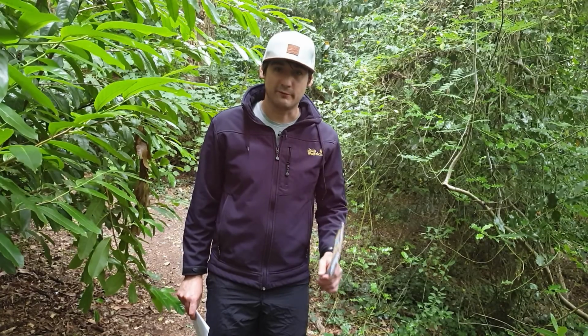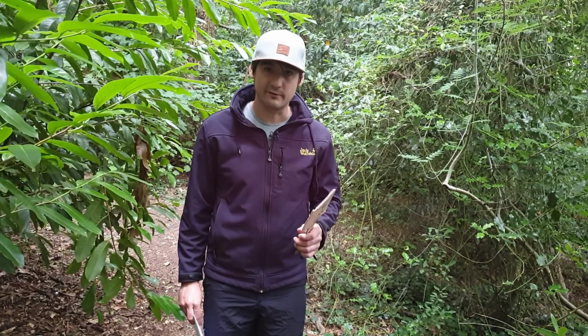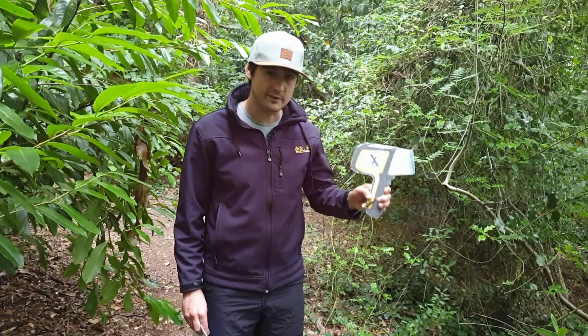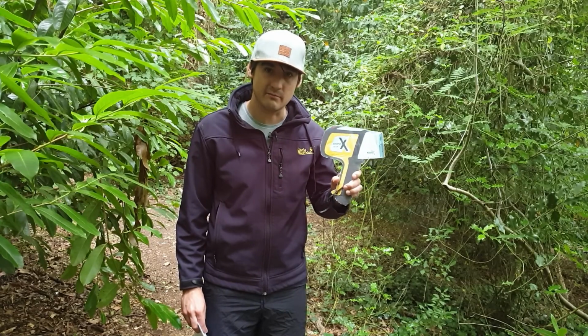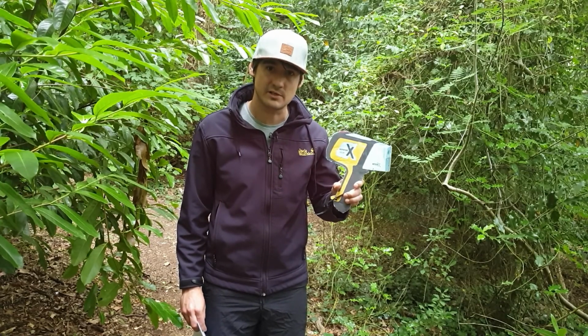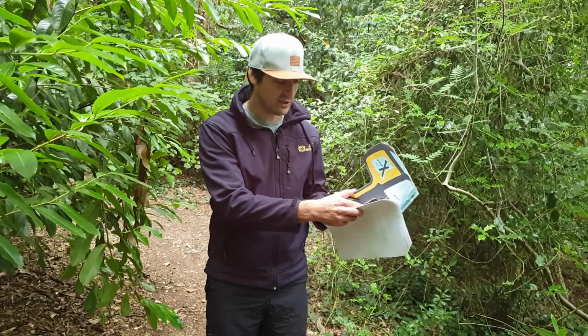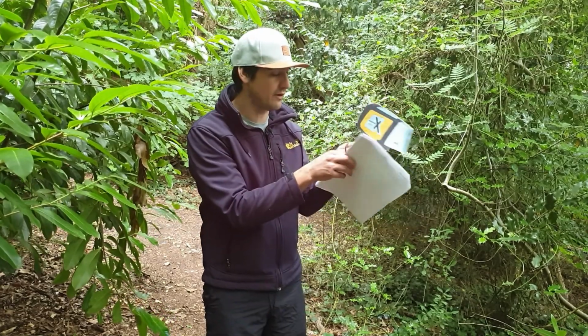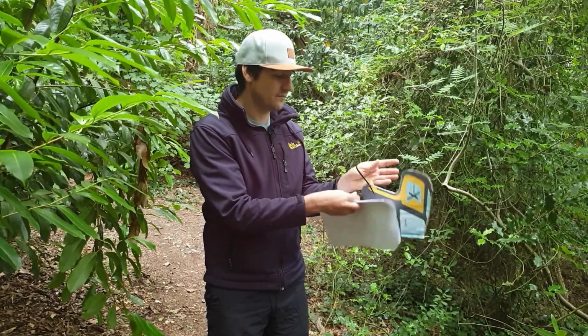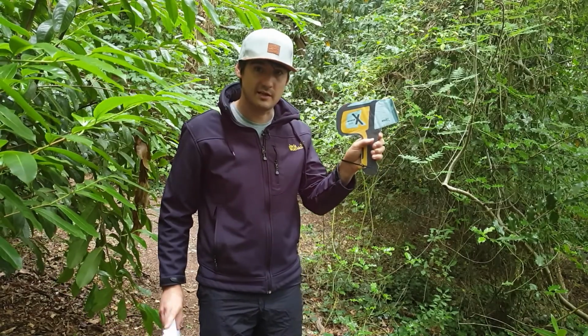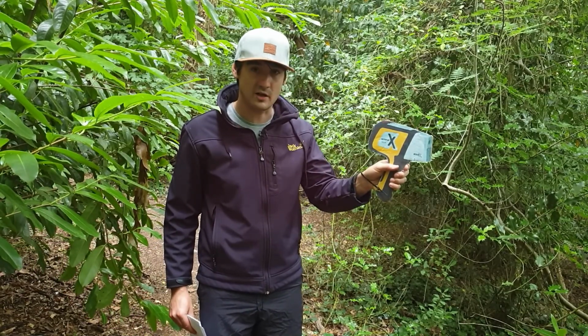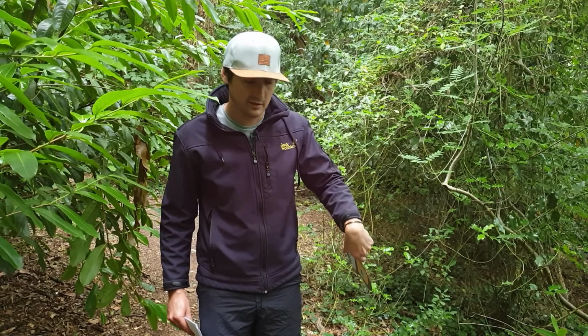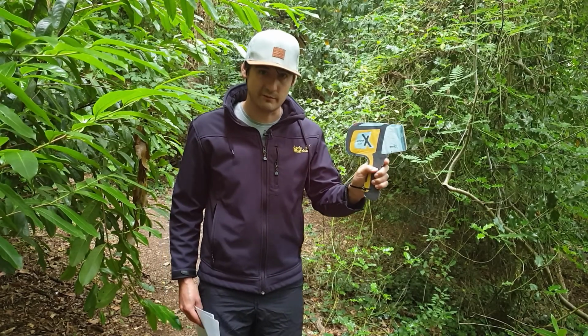Setting off. Before you set off into the field, one of the very first things you need to do when carrying the XRF, this is just a cardboard cutout that I've mocked up for this training demonstration. So the first thing you need to do is put the safety strap on around your wrist to make sure that the XRF is secure at all times in case you accidentally let go. So that's the first thing you need to do in the field.